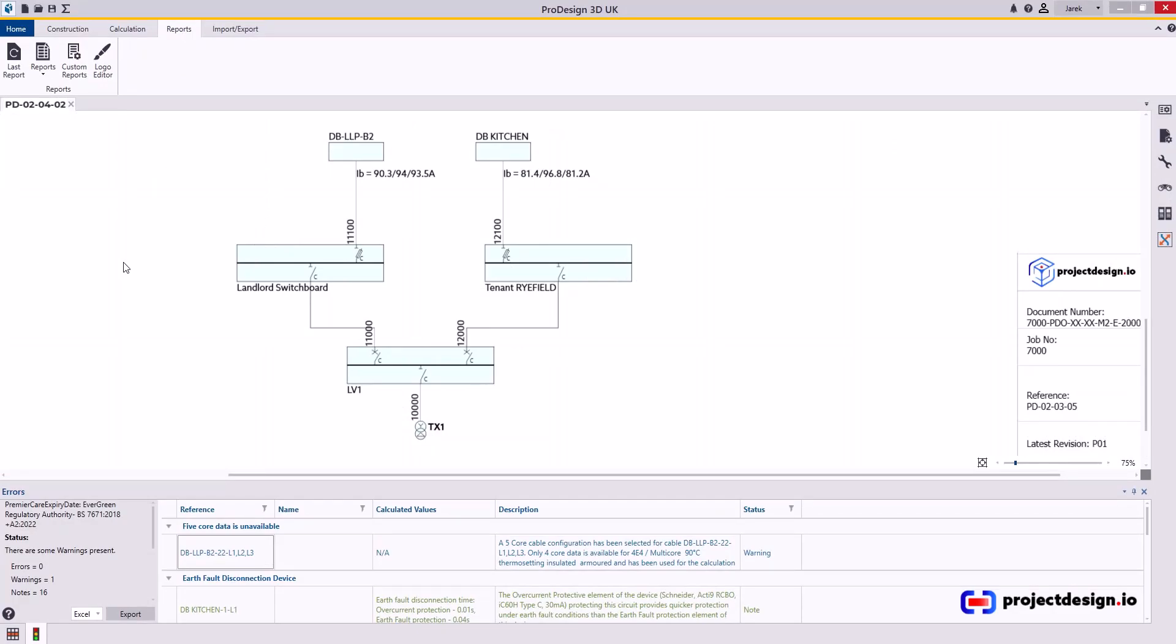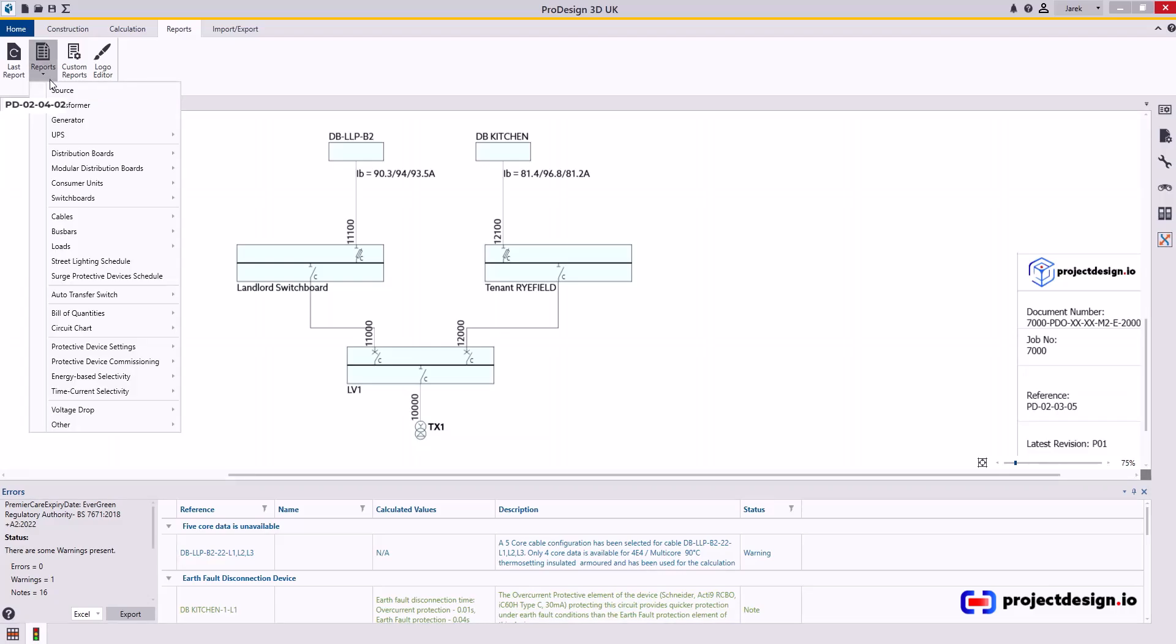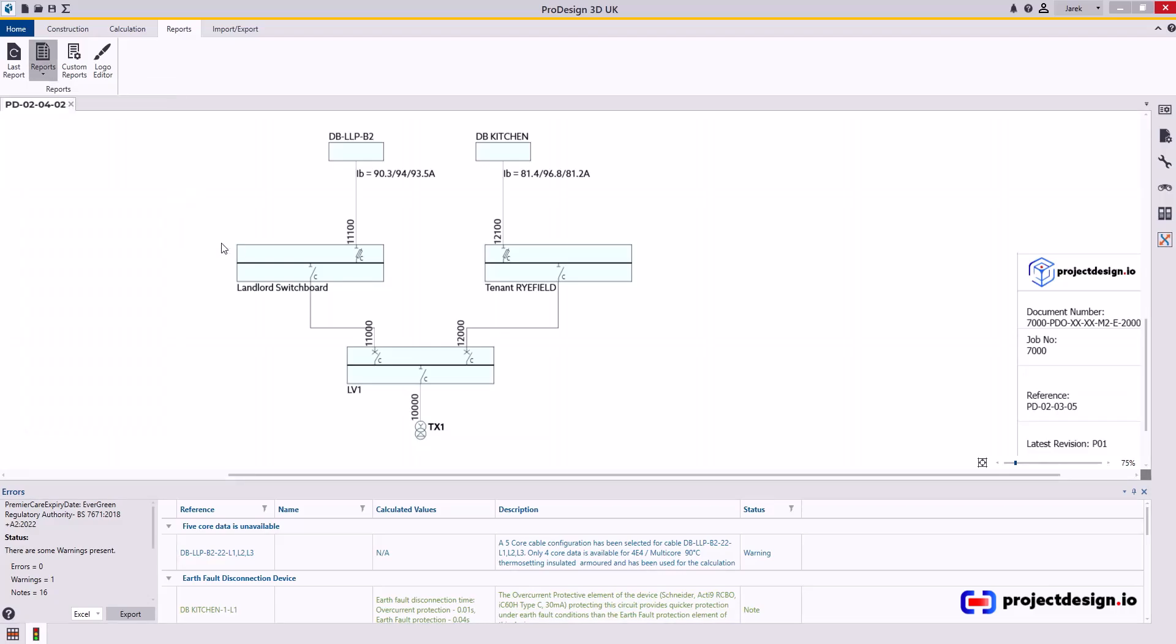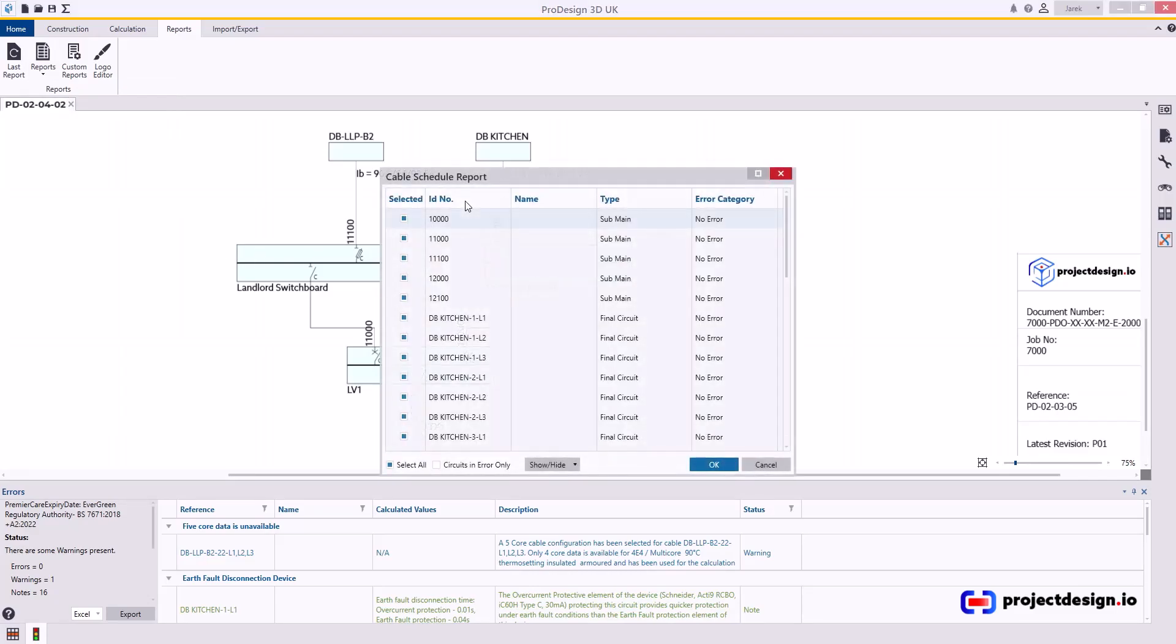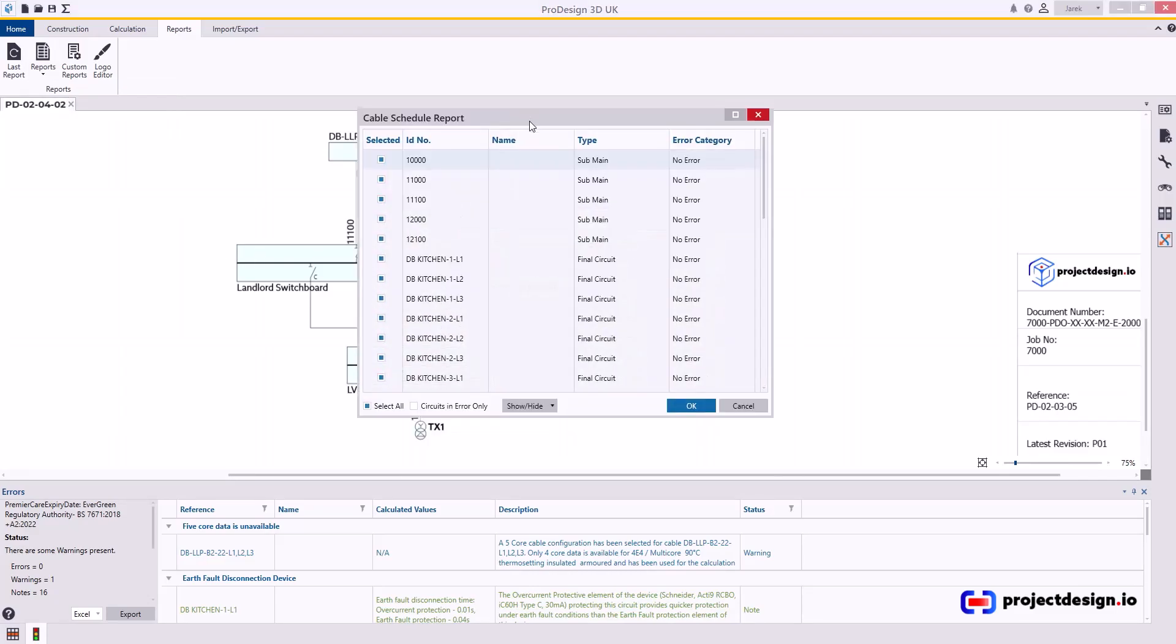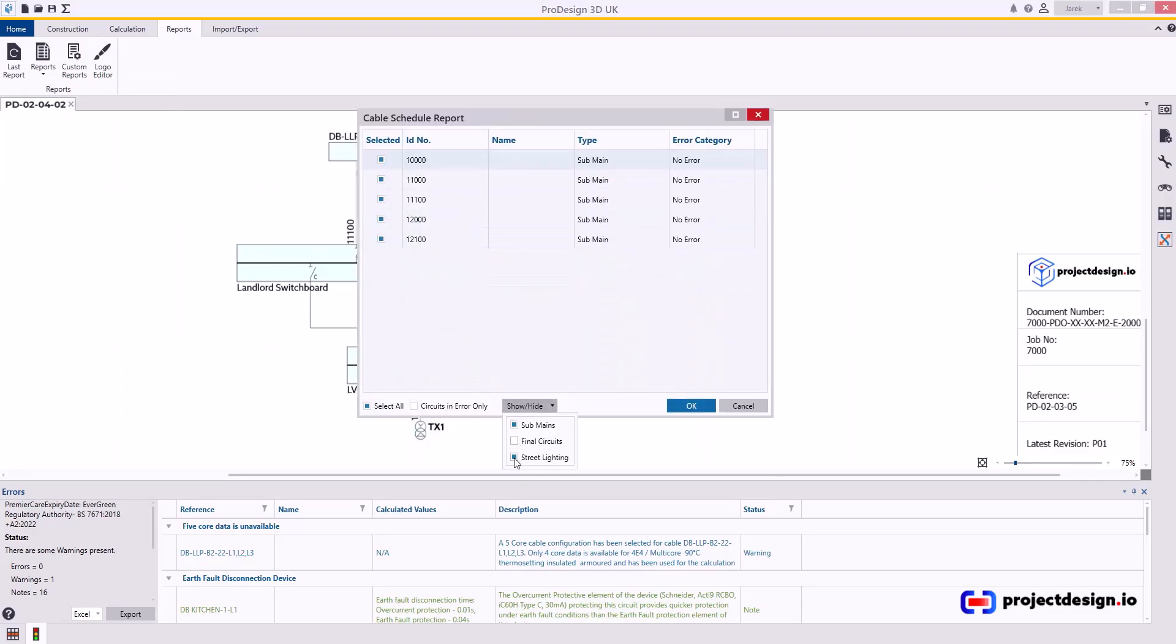To do it, go to Reports > Cables > Schedule. This is useful for sub main distribution circuits. It's pointless to print this for final circuits—you can do it using a circuit chart or distribution board schedule rather than cable schedule.